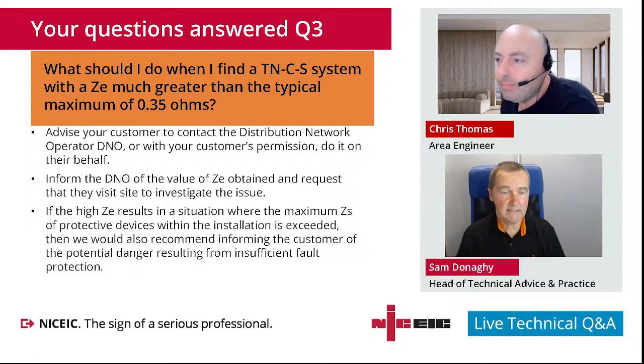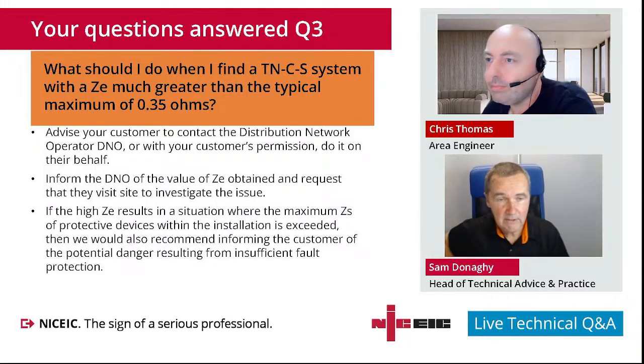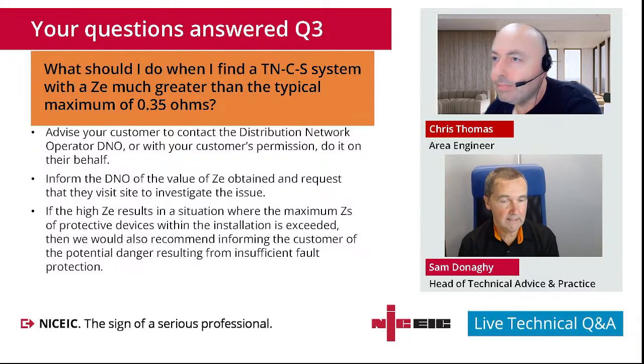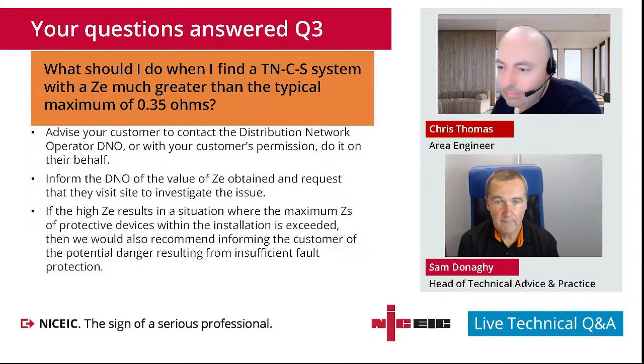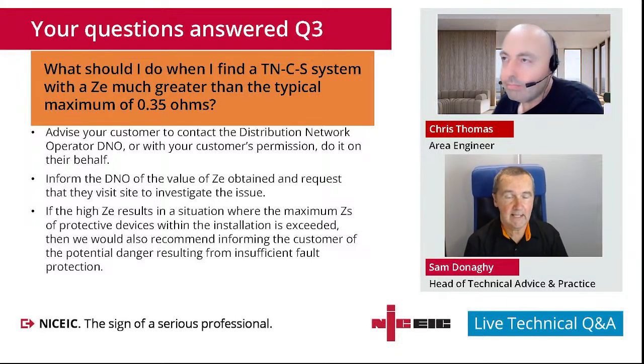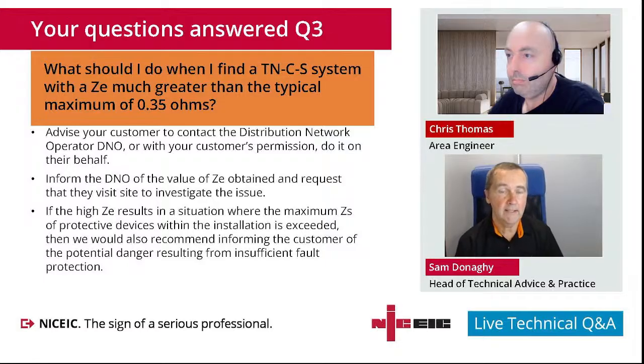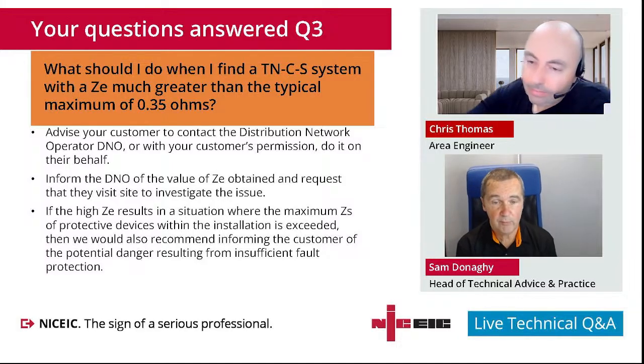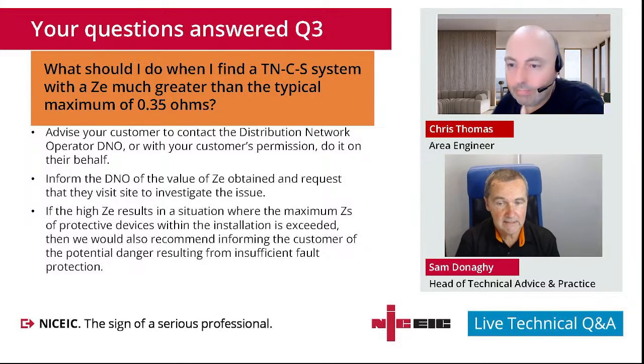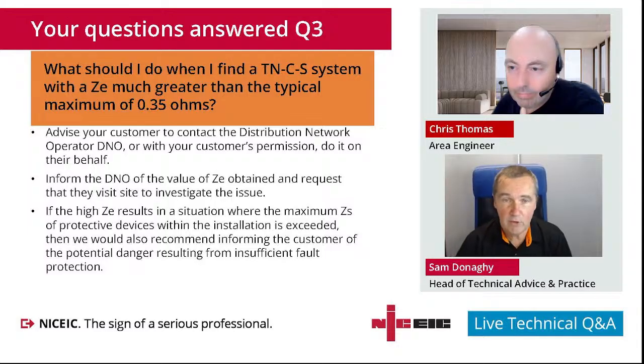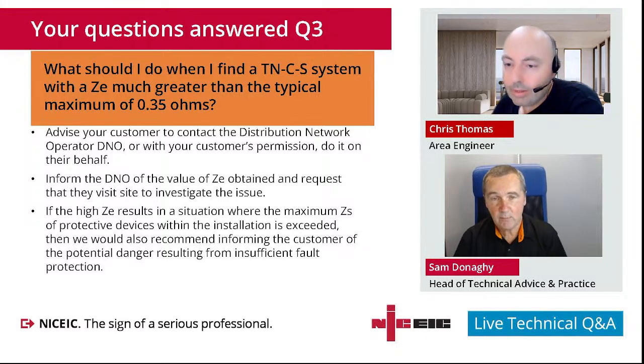Yeah, absolutely. And as I say, it's quite a common question. People get very concerned when it's over those threshold values. That in itself isn't an issue with the installation. Obviously, if the values for Ze go so high that it starts to affect the maximum Zs values for distribution circuits and final circuits, then it becomes a problem, and you would have to resolve those issues if you can't meet the maximum Zs for your protective devices to achieve the required disconnection times. So that's when it really becomes a problem.